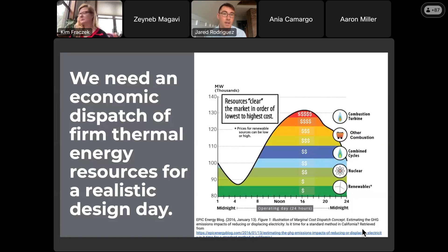So we can use that thermal dispatch approach to radically reduce peaking gas throughput, which is exactly the issue we're trying to address here, in order to reduce the redundancy in our gas system and improve resiliency against extreme cold weather events that could be coming.